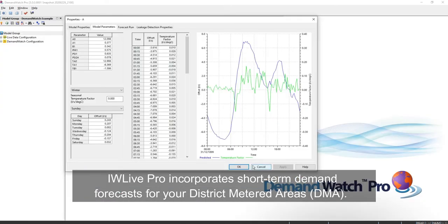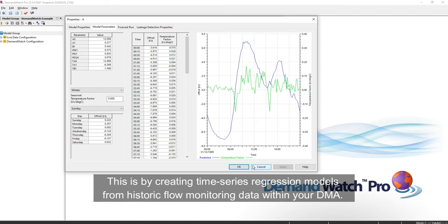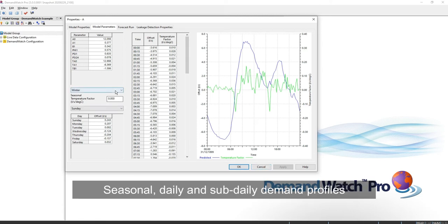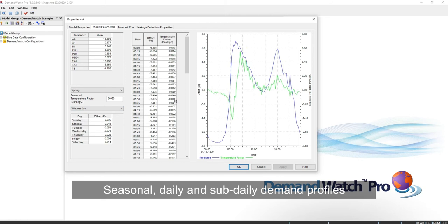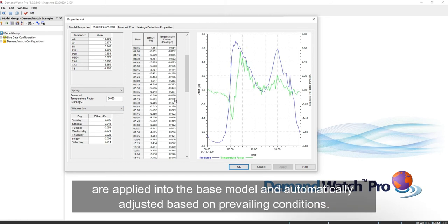IWLive Pro incorporates short-term demand forecast for your district-metered areas. This is by creating time series regression models from historic flow monitoring data within your DMA. Seasonal, daily, and sub-daily demand profiles are applied into the base model and automatically adjusted based on prevailing conditions.